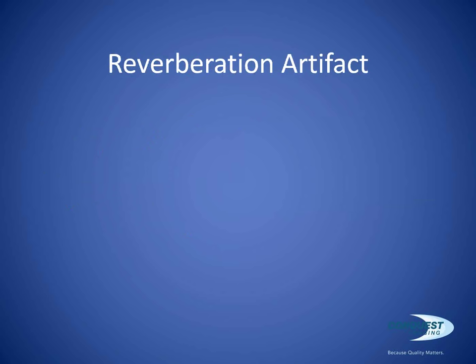Here are some common artifacts that may be reported by sonographers. These are artifacts that I've had to deal with in the past. These are not malfunctions. These are a result of physics. It's just the way the systems operate. And I just wanted to go through a couple of these, so if you do see them, you recognize them as not a malfunction of the system, but as just the way the system works. Understanding a lot of these things will help you going forward when you are troubleshooting. I've had countless tech support calls over the years where people have tried to troubleshoot problems on systems that are not malfunctions. It's just the way the system operates.